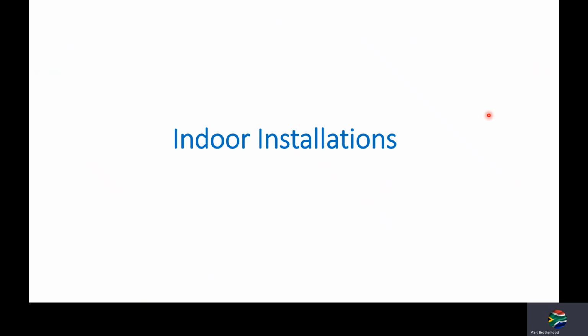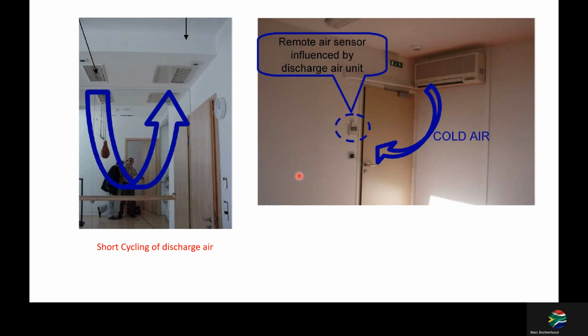If we look at some indoor units that have been installed, here we can see a supply and return grille in an office. So you're going to have short cycling of your discharge air, and it creates very poor delta Ts on your coil and gives you poor cooling effects.